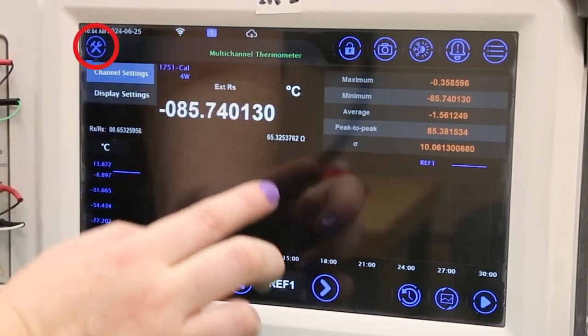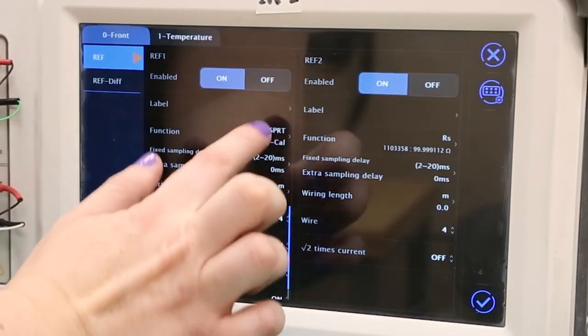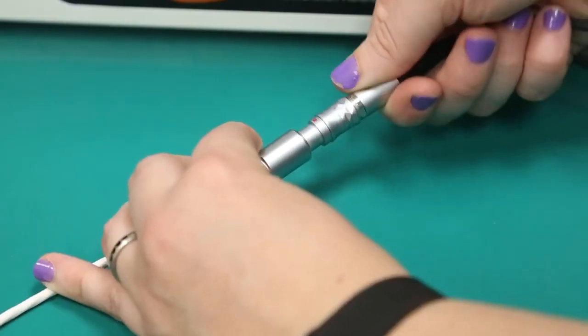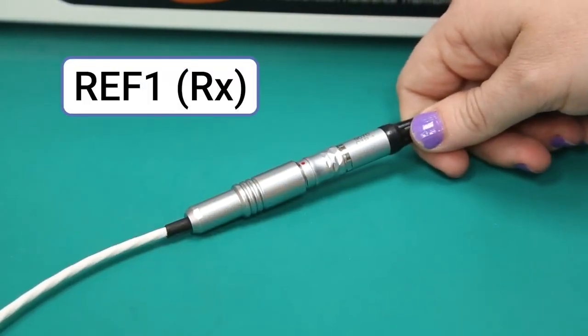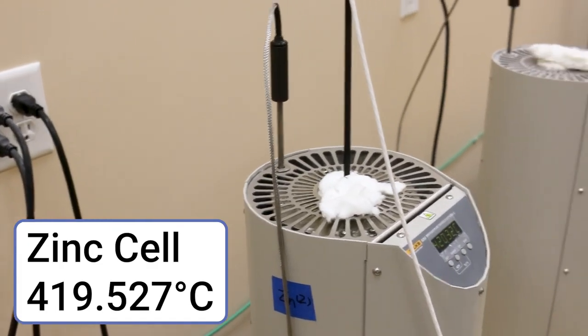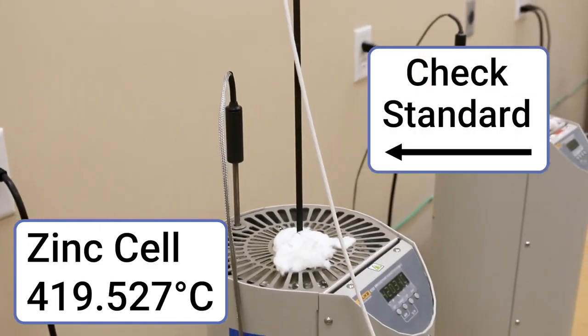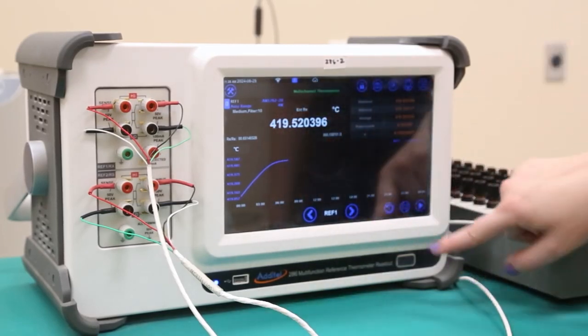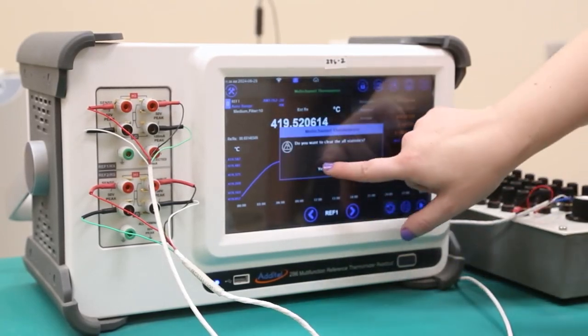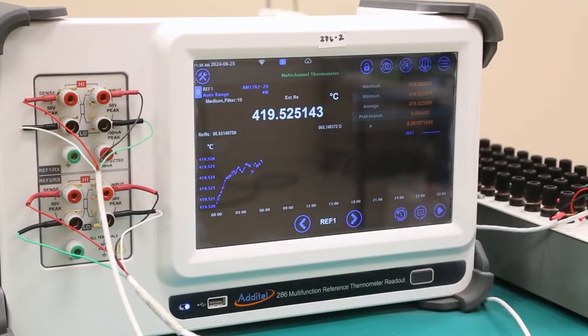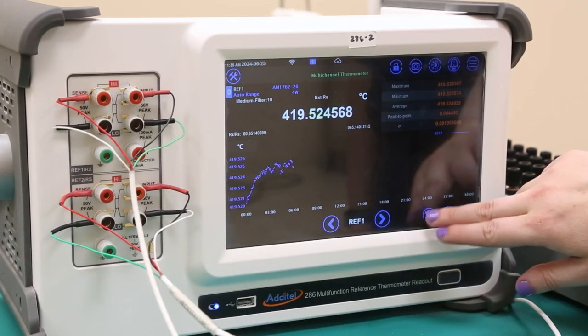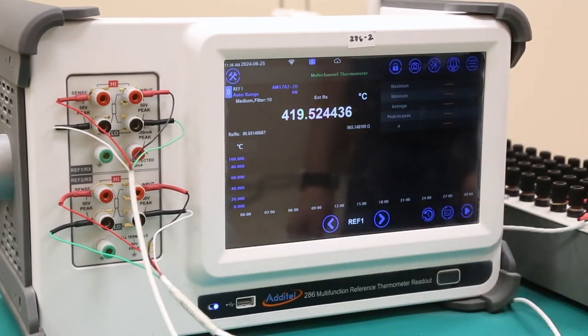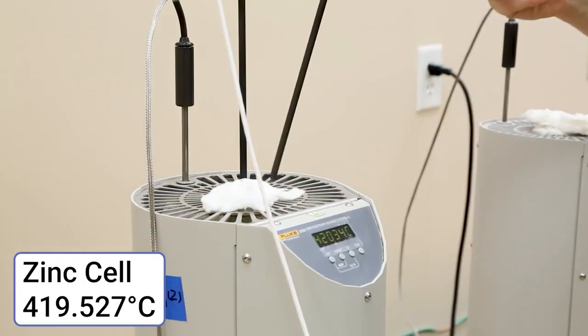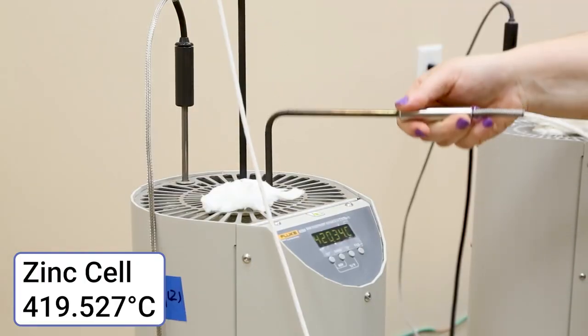To change the channel settings, select the tools icon from the top left corner. Here you can select the correct reference thermometer to check the calibration point. You should also connect the reference thermometer to the REF1 wire. Now insert the reference probe, also called the check standard, into the zinc cell. Every few minutes, we will reset the thermometer statistics to resize the y-axis on the screen. This will help us identify when the temperature has plateaued enough for calibration, as shown by the temperature graph leveling off horizontally over time.